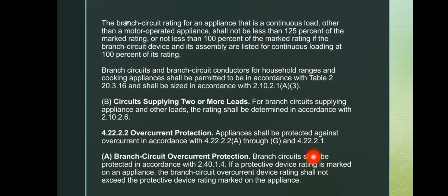And now let's look at the rules for branch circuit ratings and overcurrent protection. For appliances that run continuously and are not motor operated, the branch circuit rating must be at least 125% of the appliance's marked rating. The only time we can use 100% is when the device and the circuit are both listed for continuous loading at 100%.